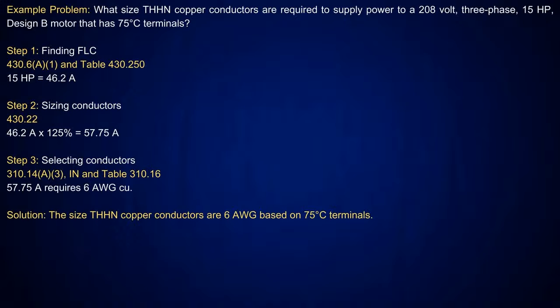This one here is a 3-phase, the exact same thing. I've got a 208 volt 3-phase 15 horsepower design B motor. Go over to table 430.250. 15 horsepower is going to require 46.2 amps. In step 2, we take it at what? 125%. That'll give me 57.75 amps. Go to table 310.16, 75 degree C column. The next size above that is 65 amps, which requires a number 6 conductor.